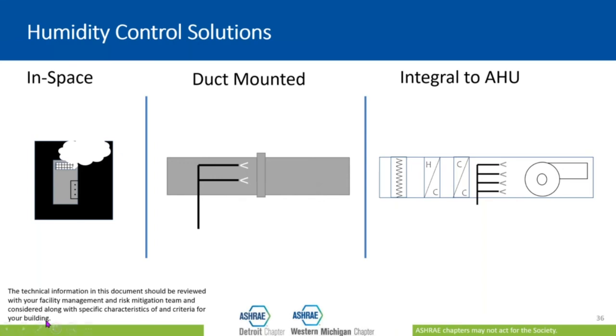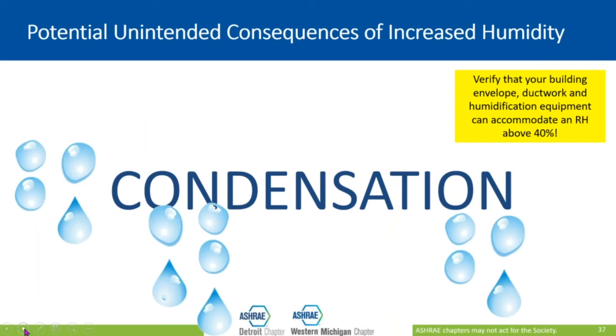When we're doing that, we want to make sure that, for example, if we're putting it in the air handler or in the ductwork, we've got enough downstream absorption to handle the moisture that would be provided by that humidification system. Whenever we're looking at humidification, the big concern is always condensation. And so you want to make sure that not just the ductwork and the equipment, but also the building envelope, consider the windows, consider the thermal insulation, and all of that, can handle relative humidity levels above 40% in the wintertime.